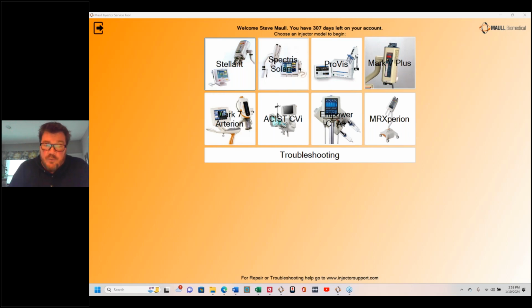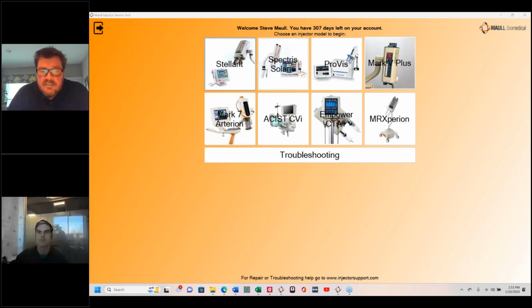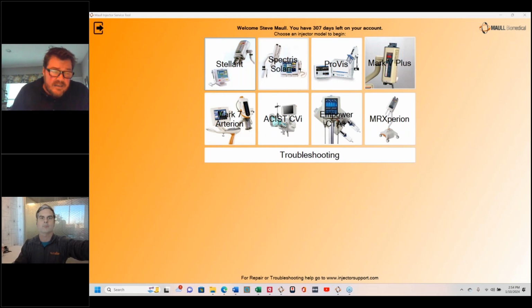What we will do, if we need to make that adjustment, is this: we obviously don't have the manufacturer's OEM software, so we will go in and physically adjust that potentiometer. If it's off, MedRad uses software to adjust it; we actually physically adjust it. There are a couple of other examples like that, but we haven't made up any procedures. Everything that we do is what the manufacturer says needs to be done. 99% of the time, we do it exactly the same way they do it. There are just some instances where we have to do it slightly differently, but we get the same results.